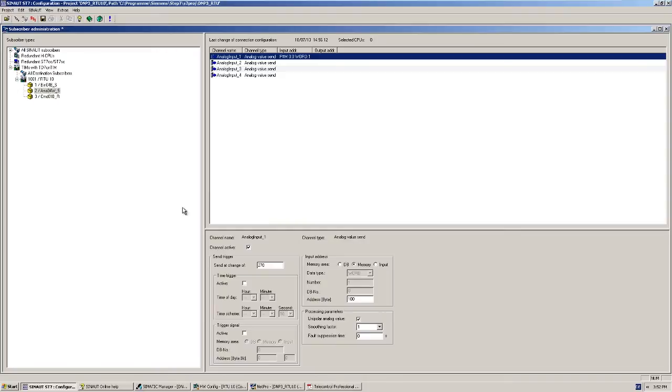Because an analog value can usually change dynamically, we assign a threshold value check to it. This prevents the value from being continually transmitted, but only when it changes, by for example 1% of the valid measurement range. Since our analog values move in a range from 0 to 1000, a threshold value of 10 equals exactly 1%.